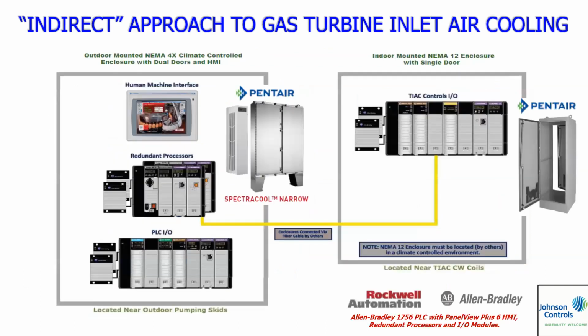All right, again, same approach on the controls. Same identical approach. The only difference is instead of just the pumps and air-cooled chillers, we're doing both chilled water and condenser side pumps and the fans on the fan coolers. That's all we're doing, extra points.